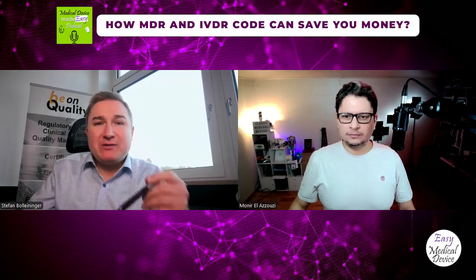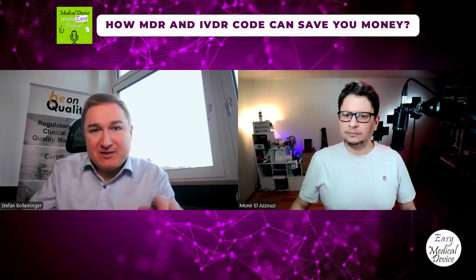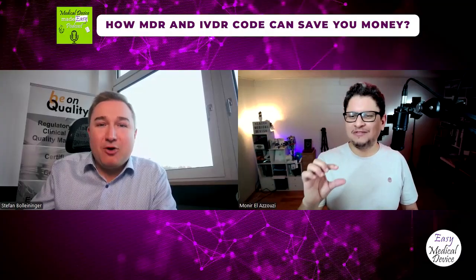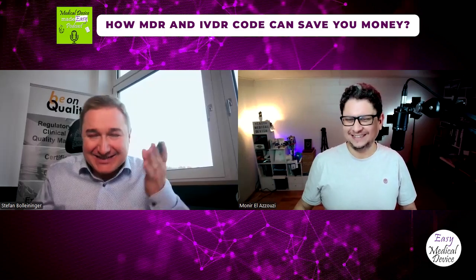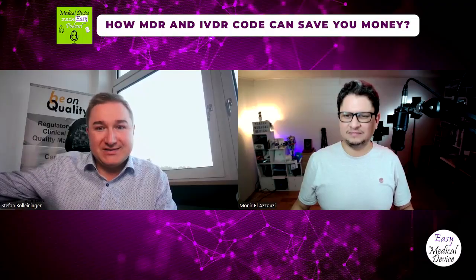And one thing I want to add on that, especially when you talk about startups, they tend to build the biggest and greatest products they can. Based on certification, that's a very bad idea. Yeah. Do the minimum viable product. Exactly. The smallest product fulfilling the intended purpose. That's the one for certification. During the certification time, you have for the initial certification, 12 to 18 months to make the product bigger. And based on your sampling, you can put it then on the list.